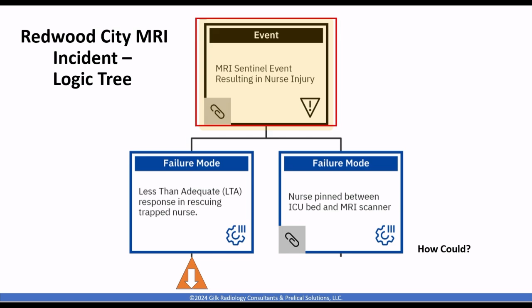They didn't quench, and they forcibly removed the nurse from the bed. They didn't quench, as Toby told you. There was a technologist who chose to not quench the magnet, believing that they needed approval to do so. So as I go down from that decision, I'm going to look at there was less than adequate guidance on the quench authority. They didn't think they had the authority to do it, so therefore they didn't do it. And then I'm not going to get into the corrective actions that Toby's working on.